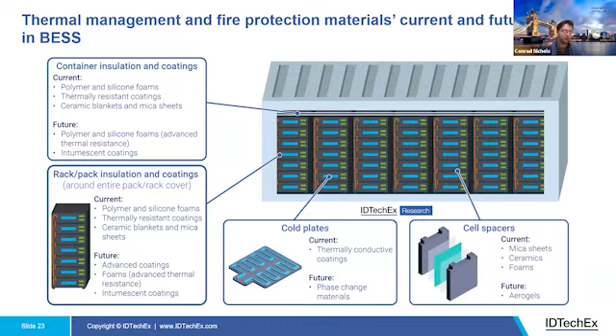And in the future, we could expect intumescent coatings to be applied, and these are coatings which form a char upon exposure to heat. However, post-processing to remove the char can be quite challenging. And at the container level, lining the inside of the container could also be an option. And you could do this with insulation materials, again, to contain heat and prevent flames from reaching outside of the container. And here we could expect materials such as foam, ceramic blankets, and mica to be suited, along with intumescent coatings for advanced flame retardancy.